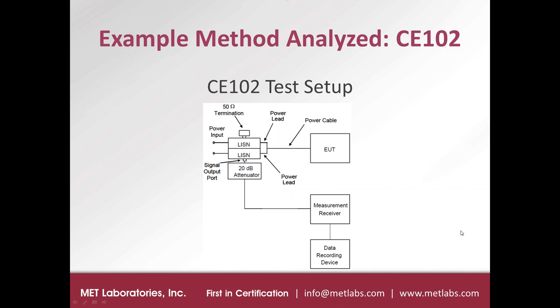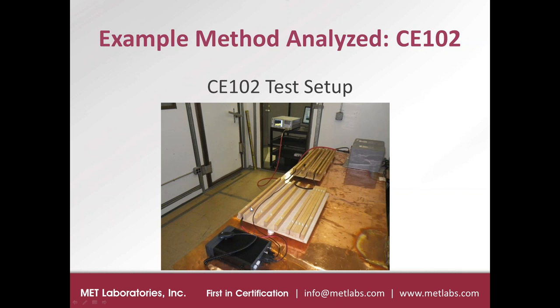And then the EUT needs to be powered up and operating per its normal use. Here's a photograph of the setup showing a radio that was under test here, and then the supports used to insulate the EUT cables from the ground plane. And down here are the LISNs, and this red coaxial cable is connecting to the measurement port of one of the LISNs. The other end of that coax cable is connecting to the input of the spectrum analyzer. And then also on this cart out here, there's a computer down here, and you can see a piece of the monitor up there that has the control software on it for the test.